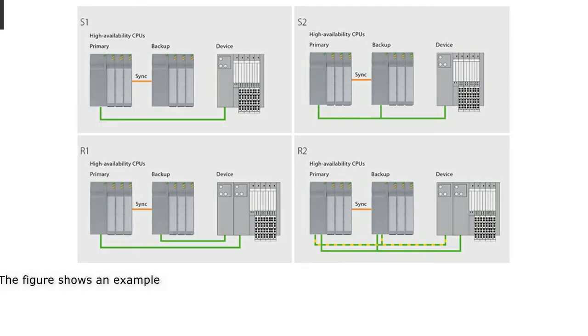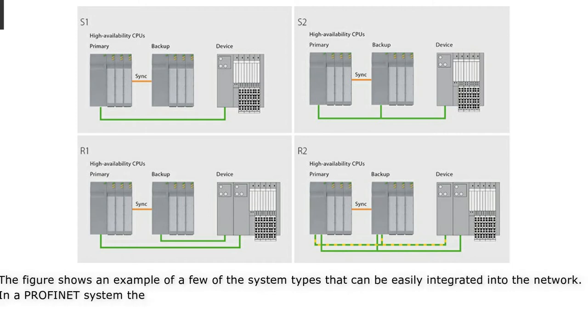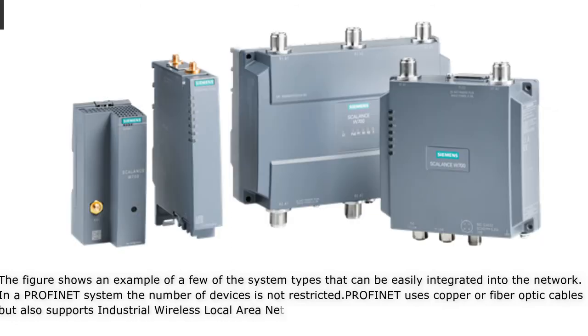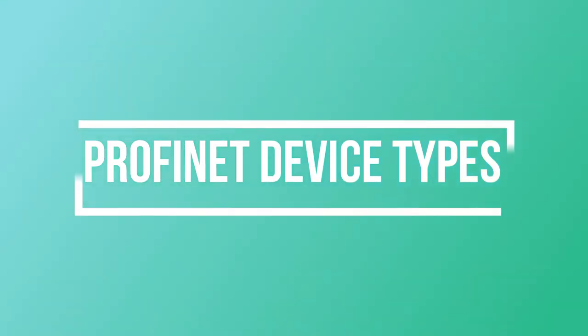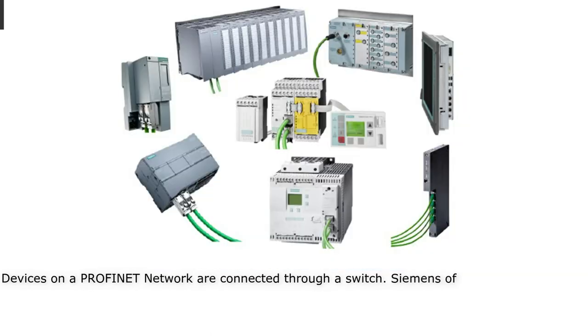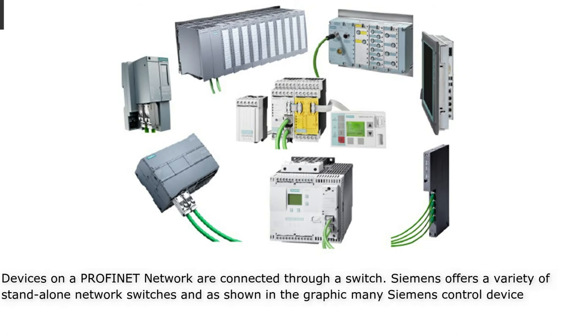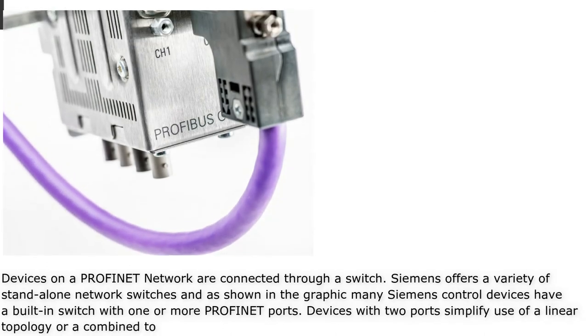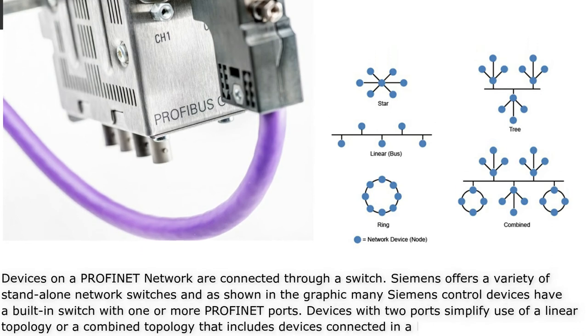The figure shows an example of a few system types that can be easily integrated into the network. In a Profinet system, the number of devices is not restricted. Profinet uses copper or fiber optic cables but also supports industrial wireless LAN communications. Devices on a Profinet network are connected through a switch. Siemens offers a variety of standalone network switches, and many Siemens control devices have a built-in switch with one or more Profinet ports. Devices with two ports simplify use of a linear topology or a combined topology that includes devices connected in a linear manner.